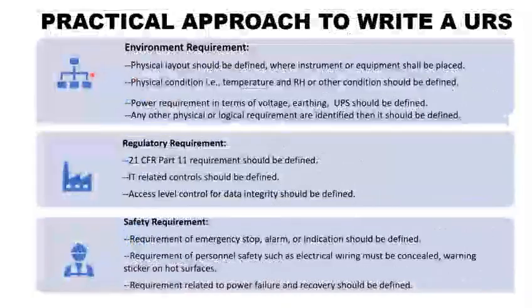Next is environment requirements. The physical layout should be defined where the instrument or equipment shall be placed. Physical conditions such as temperature, relative humidity, or any other required conditions should also be defined. Power requirements in terms of voltage, earthing, and UPS (uninterrupted power supply) should also be defined, along with any other physical or logical requirements.